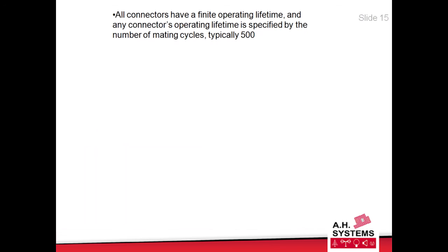It's a truth that all connectors have a finite operating lifetime. Any connector, of whatever standard, is usually specified by the number of mating cycles. A typical one in our industry, the EMC industry, would have around 500 mating cycles. So if you've got a 10 or maybe even 15-year-old chamber, there's a good chance you're close to or have exceeded those 500 mating cycles.